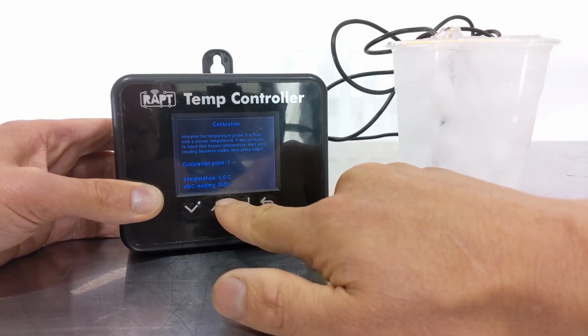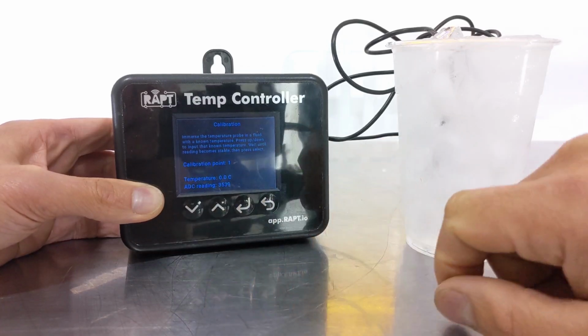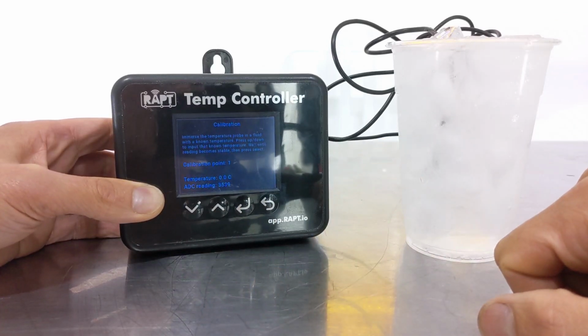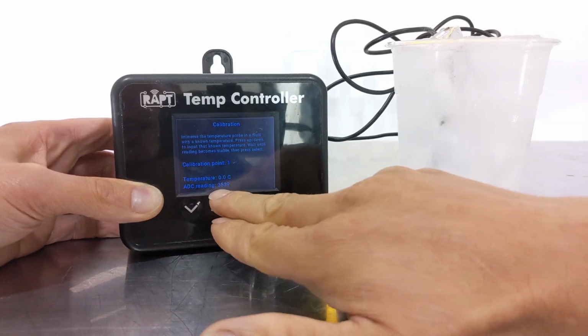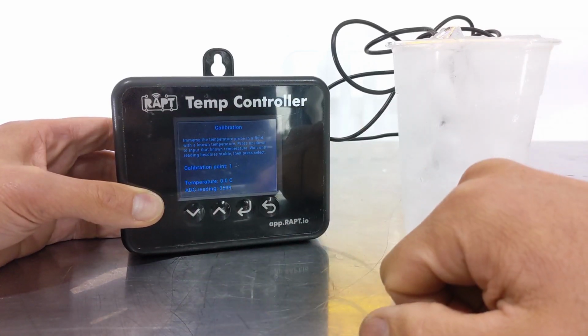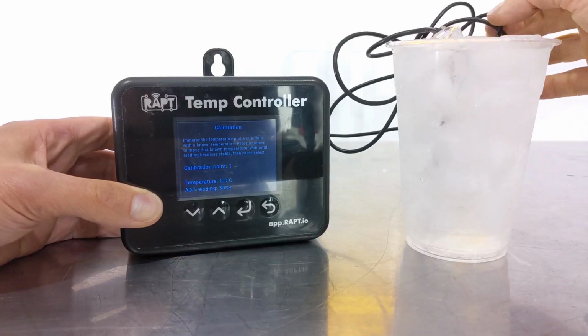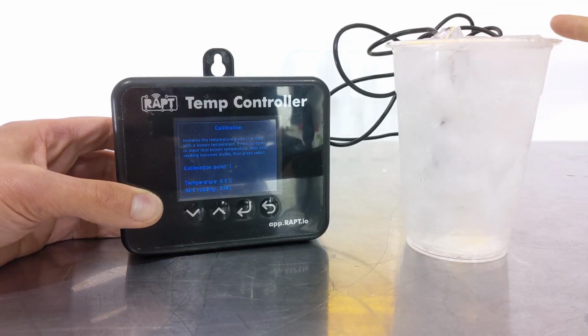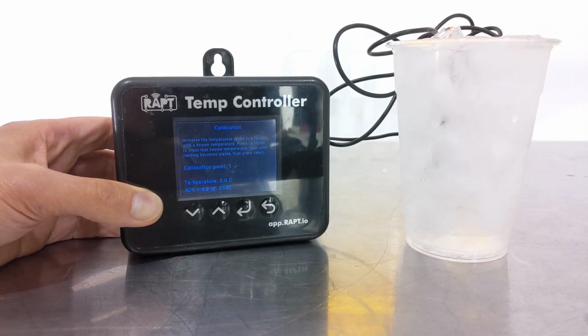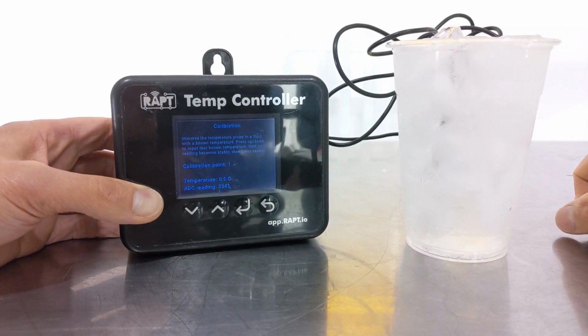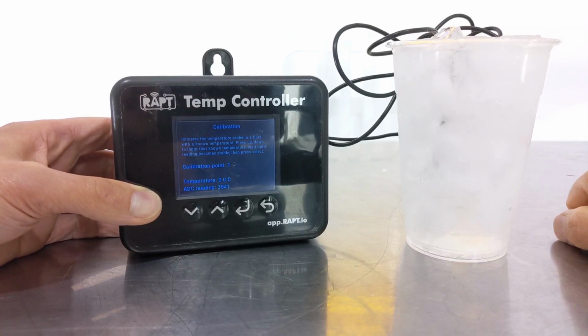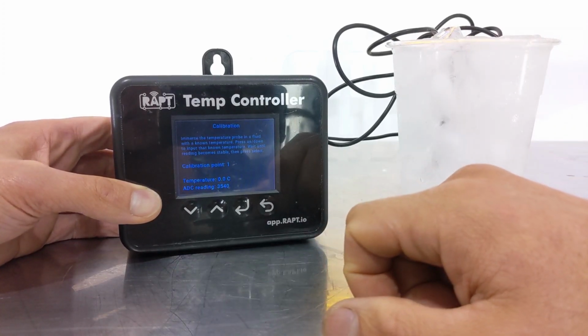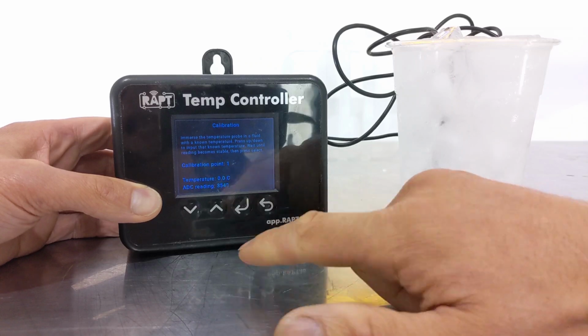See, it's kind of stabilized at 3539, and it's been sitting there for a little bit now. You might get a slightly different result. It just depends on the cable. So for instance, if the cable starts to get a bit old and damaged, you might have a slightly different resistance on the cable and therefore have to do this process again, unfortunately, but that is just, I guess, the limitations of using an NTC probe.